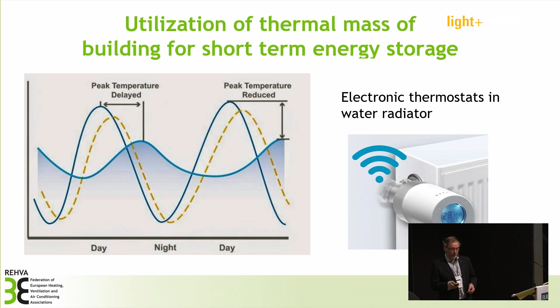Then the other option is that we have short-term energy storage in the building. So we have a small water tank that we are charging, and in this way we can cut the peaks. And in this case, we have a water tank that is integrated with the district heating substation, so that we are charging it and then using this energy when the energy price is very expensive, for domestic hot water, space heating or the ventilation system, based on the demand.